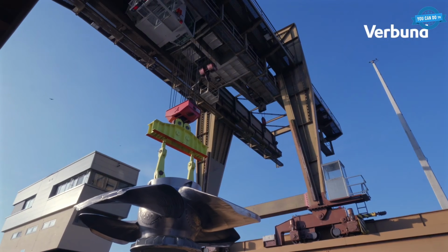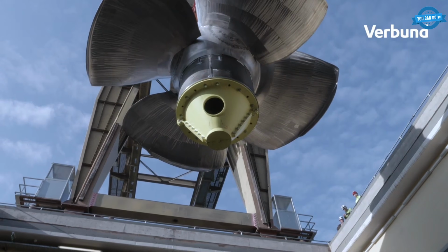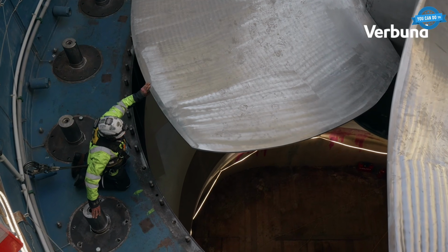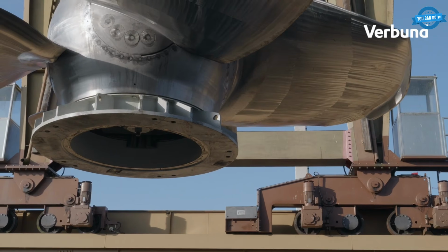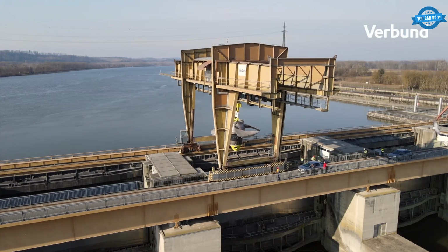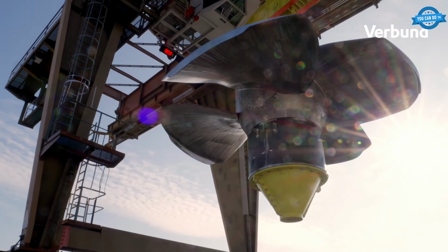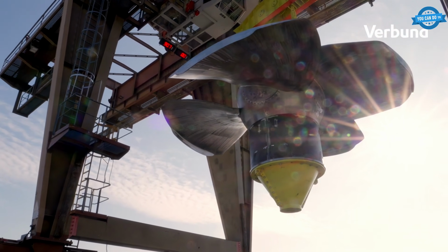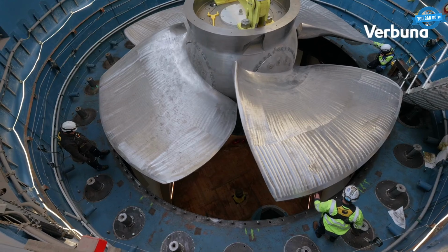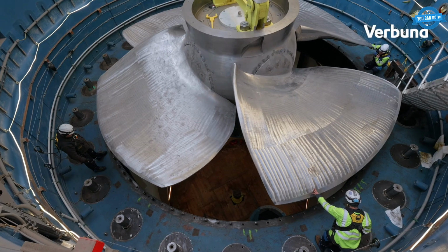Lift a 95-ton Kaplan runner into a turbine pit with 3.9 millimeters of clearance. That test runs every revitalization. The 7.8-meter runner at Walsee Mitterkirchen drops in by crane, watched down to the millimeter.